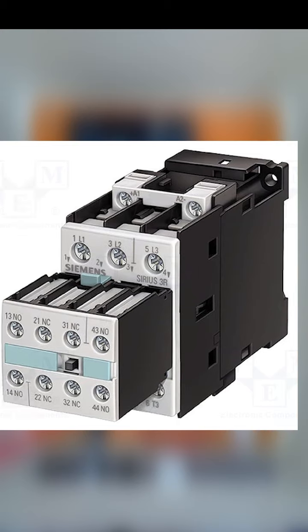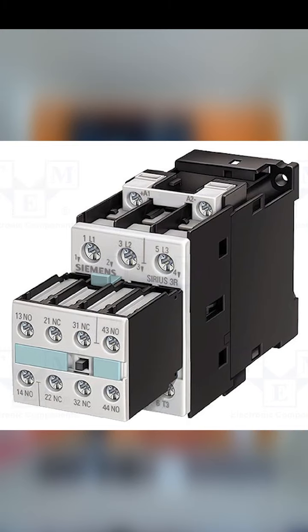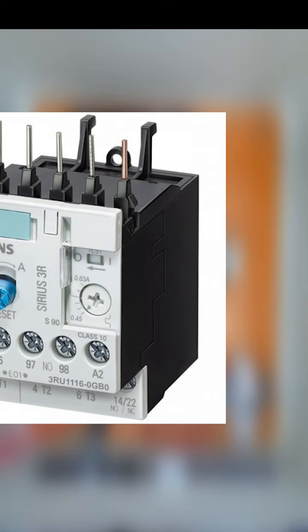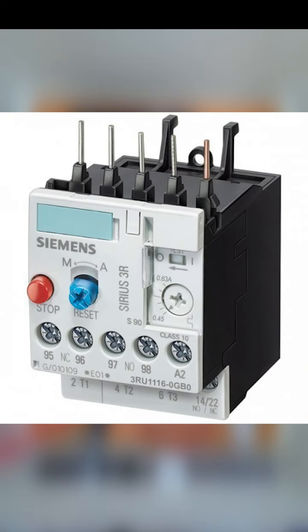The contactors are electrically operated switches that provide a safe and convenient means for connecting and interrupting branch circuits. These contactors are an economical means of starting and stopping motors and have the advantage of being controlled remotely. The contactor has three main normally open contacts and four lesser power rated contacts named auxiliary contacts used for the control circuit.